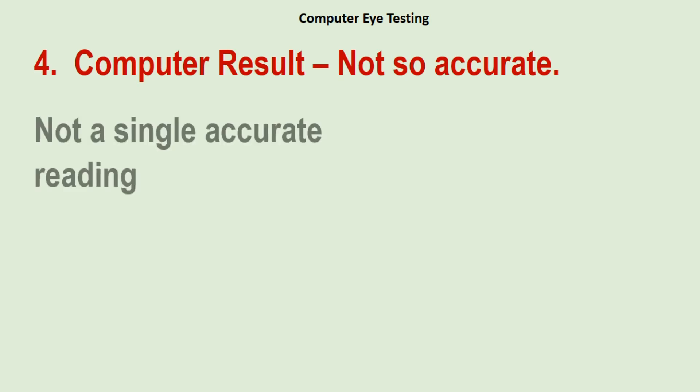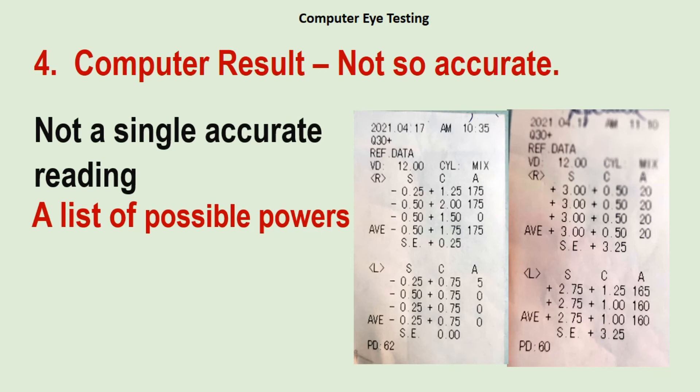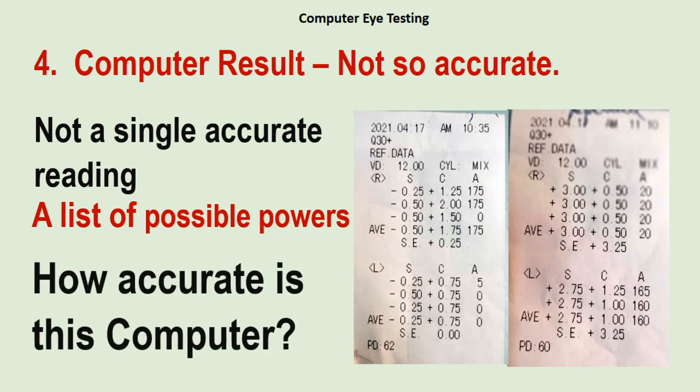Regarding computer result accuracy — it's not very accurate. Have you ever looked at the printed result slip that comes out of the machine? You will find that it does not give a single accurate spectacle power; it gives at least five different readings. The examiner cannot straightaway prescribe spectacle power based on these results. The examiner has to examine the individual subjectively, based on multiple readings, and then select one for the glass prescription. So the question arises: how accurate is the auto refractor?